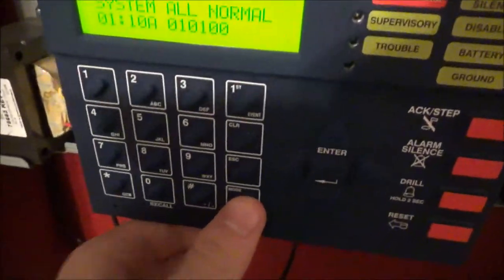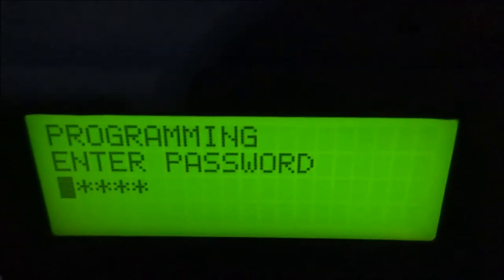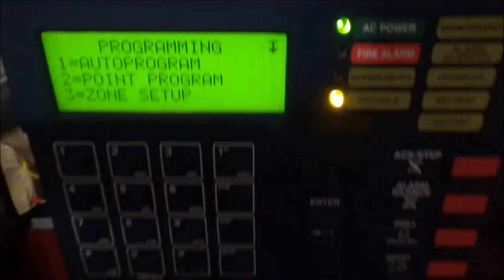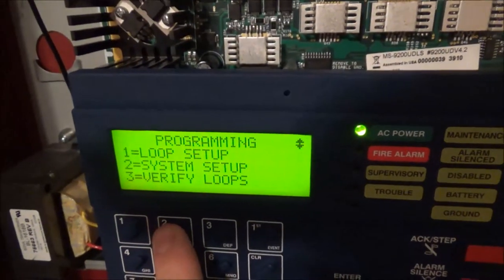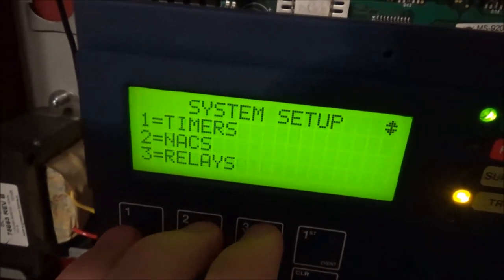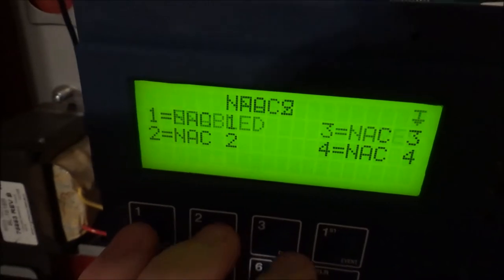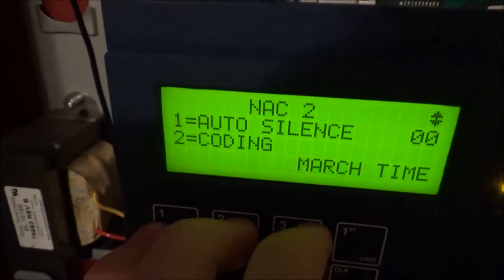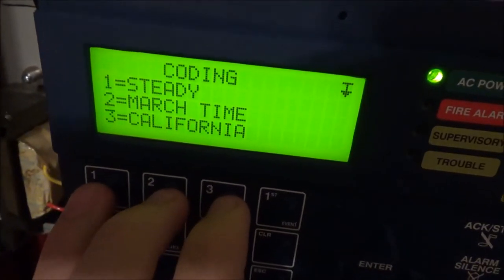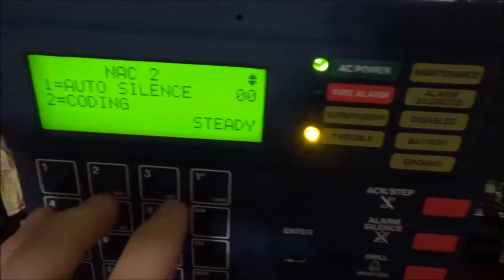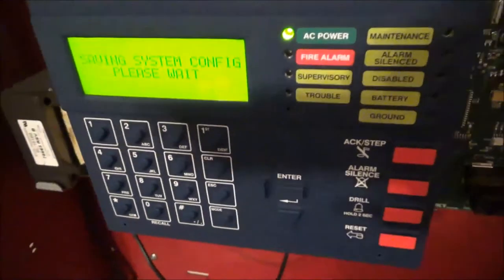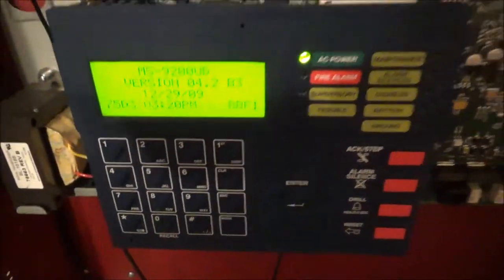Alright. Now enter programming - all you got to do is press mode or enter and then you got to hit 2 and you got to put in your password. Even though mine is the default, I don't feel like showing the default because I don't want to be held responsible for anything. Let's see, scroll down. NACs. See, NAC 2 is my horns. Scroll down. Alright, coding. We will do, since it's right there, steady, which is continuous. But now it's got to initialize again.